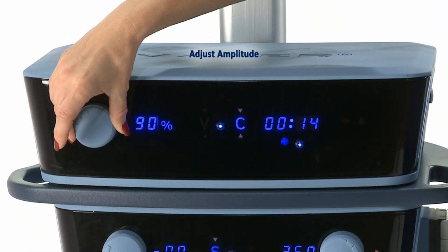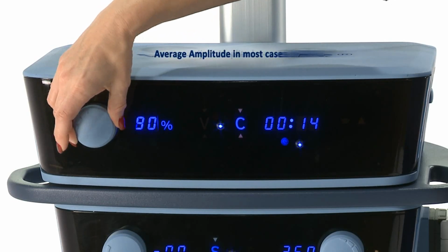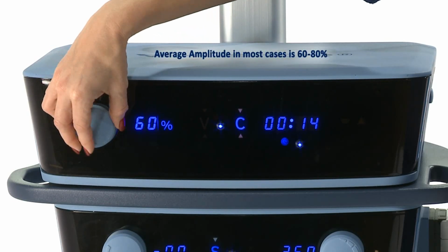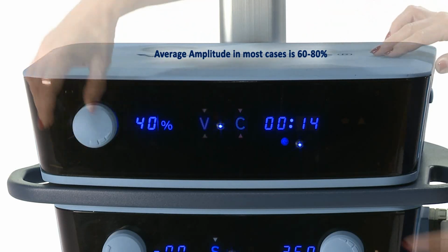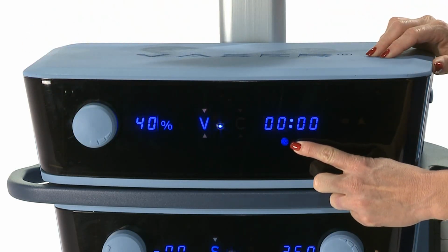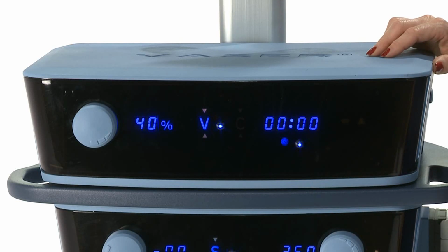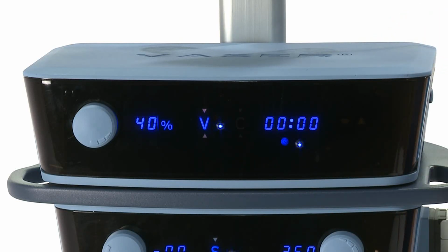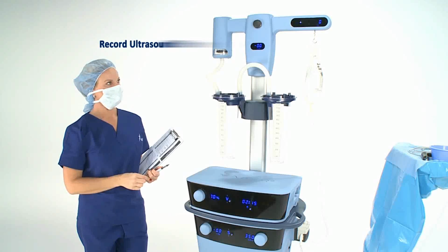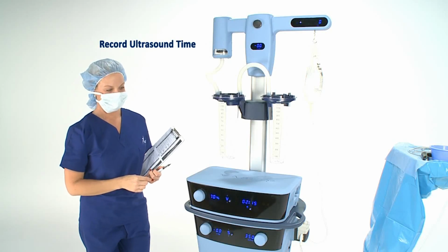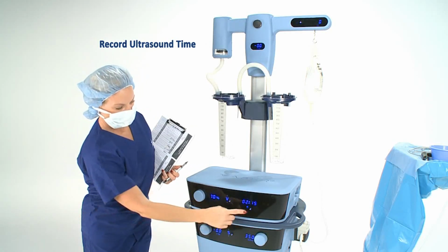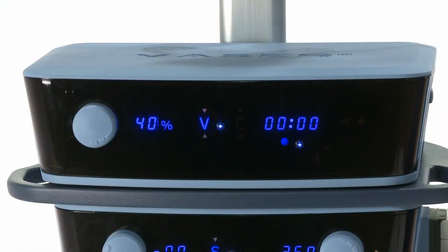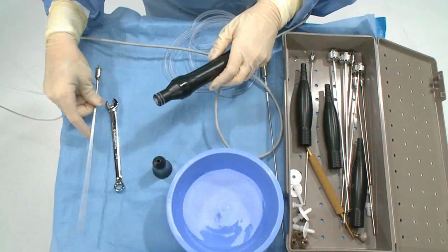Adjust the vibration amplitude, which is the percentage of power being used, by turning the amplitude control knob on the Vaser amplifier. The Vaser timer displays the total time of ultrasonic vibration activation. You can easily record the activation time for each area of the body by noting the accumulated time and then pressing the timer reset button to return the timer to 0. Time is one indication of how long the surgeon should apply ultrasound. The point at which the surgeon no longer feels any resistance is another.